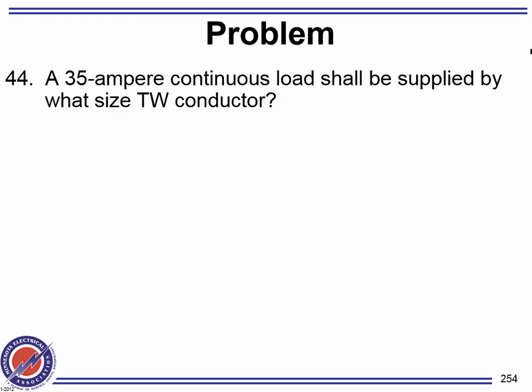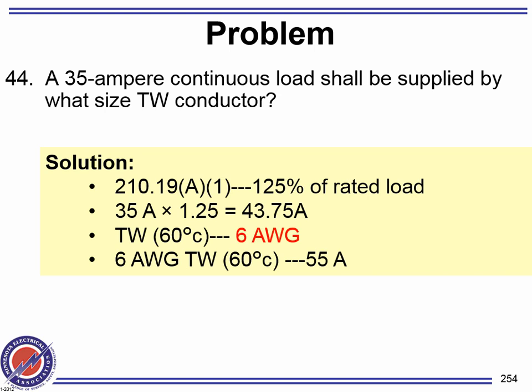All right, I have a 35 amp continuous load. What shall it be supplied by? Continuous load is not derating. It's a normal operating condition for the conductor. So when you size for continuous load, don't only look at the temperature of the conductor. You have to look at the lugs and everything else. All right, 35 amp, TW. Which column should you go to from the get-go? 60. You have no choice. So it's continuous, so multiply by 1.25, gentlemen. You've got yourself number 6.